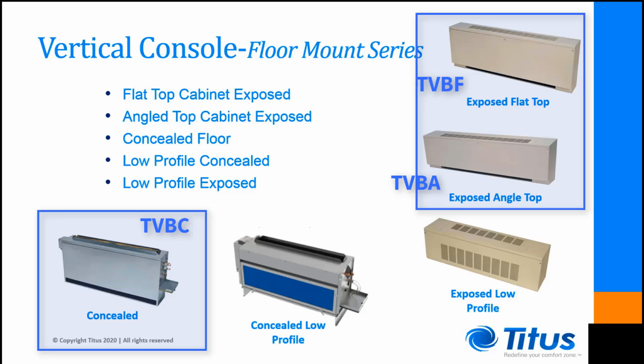The TVBF, unfortunately, does have a flat top and can be used improperly as a shelf of sorts, but the advantage it has over the TVBA is it is approximately 3 inches shorter. This flat-top console unit would be better suited in office spaces where adults will be present and should be more mindful of accidentally blocking off the supply air opening.